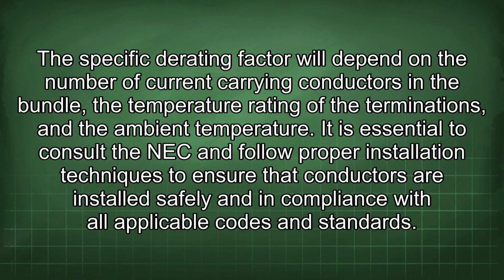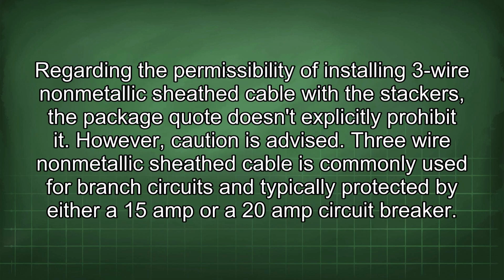The specific derating factor will depend on the number of current-carrying conductors in the bundle, the temperature rating of the terminations, and the ambient temperature. It is essential to consult the NEC and follow proper installation techniques to ensure that conductors are installed safely and in compliance with all applicable codes and standards. Regarding the permissibility of installing 3-wire non-metallic sheath cable with the stackers, the package quote doesn't explicitly prohibit it.